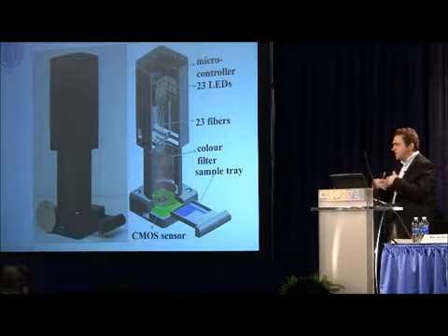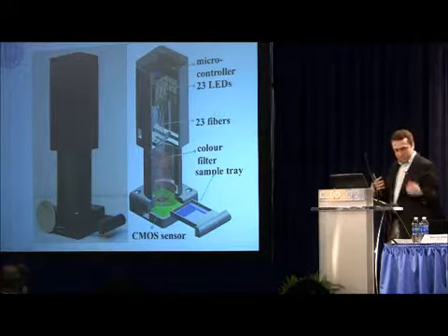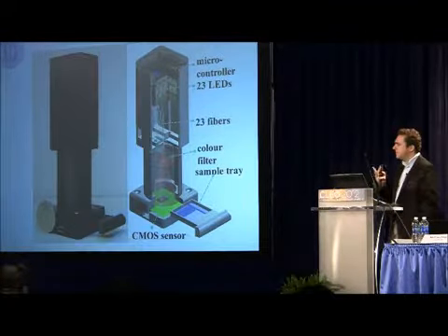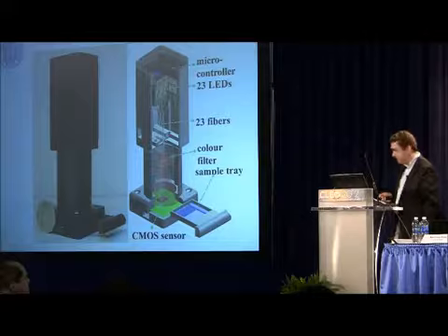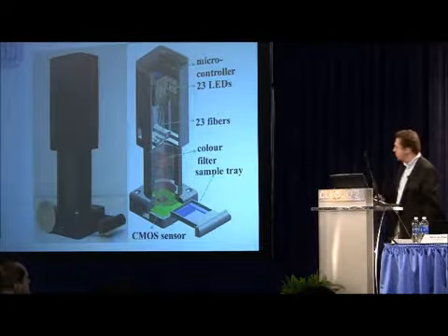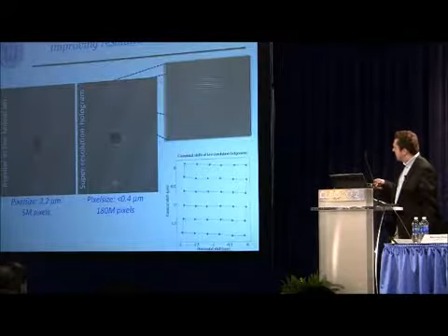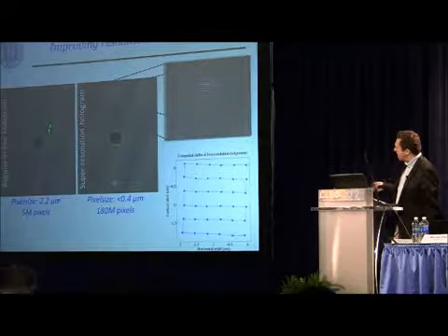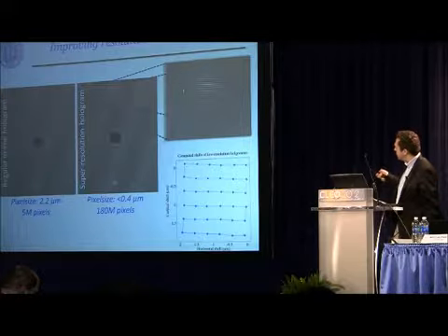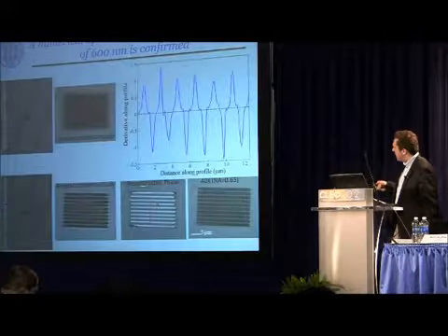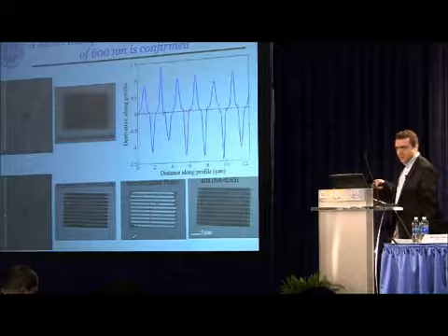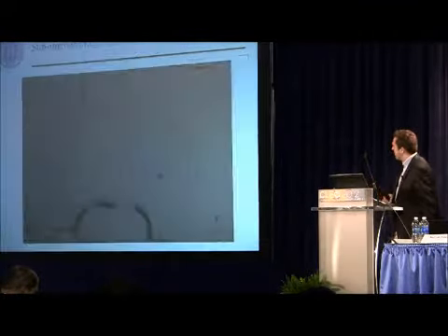And then you can synthesize a super-resolution, pixel super-resolution image, which now contains a much smaller pixel size, which can now resolve much smaller features, oscillations of these holograms, to increase the numerical aperture, to increase resolution, without sacrificing the field of view. So that's actually shown here, where with a pixel super-resolution lens-free microscope, we can now see much higher fringes, which translate into a higher resolution, deeply submicron. In this case, actually around 0.6, but recently even less than that. And of course, while we are doing that, we don't sacrifice the field of view.